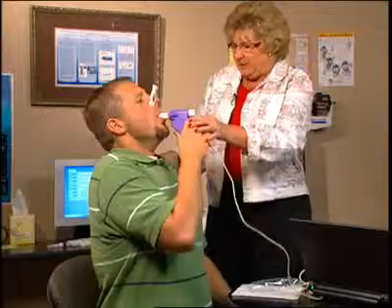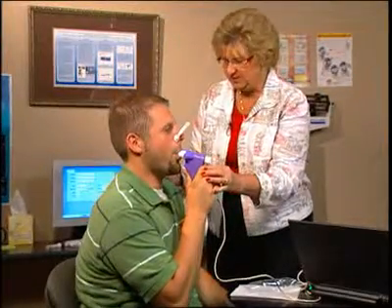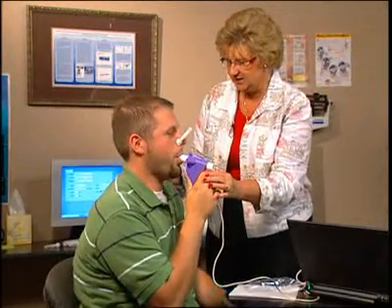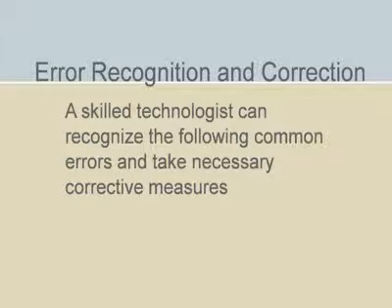With proper instruction and coaching, almost all patients can perform spirometry that is acceptable and repeatable. The causes of failed test performances can usually be identified. Then, with re-instruction and good patient-technologist interaction, they can be corrected. We'll look at some of the errors that lead to failed spirometry testing sessions.